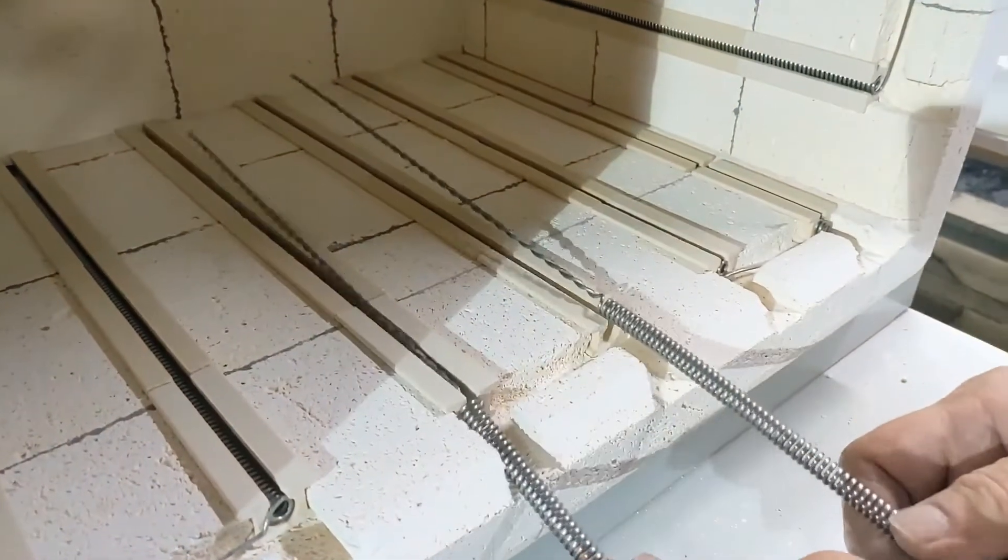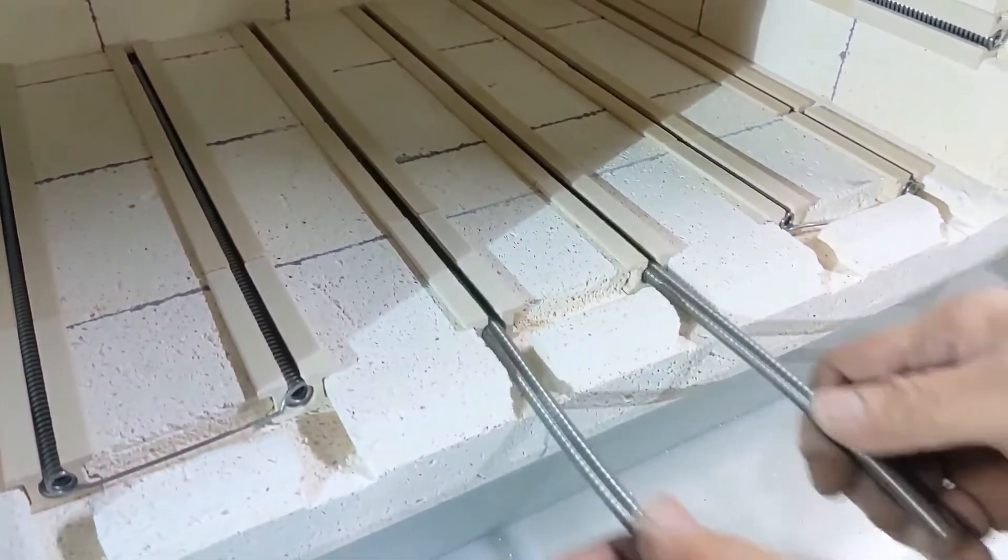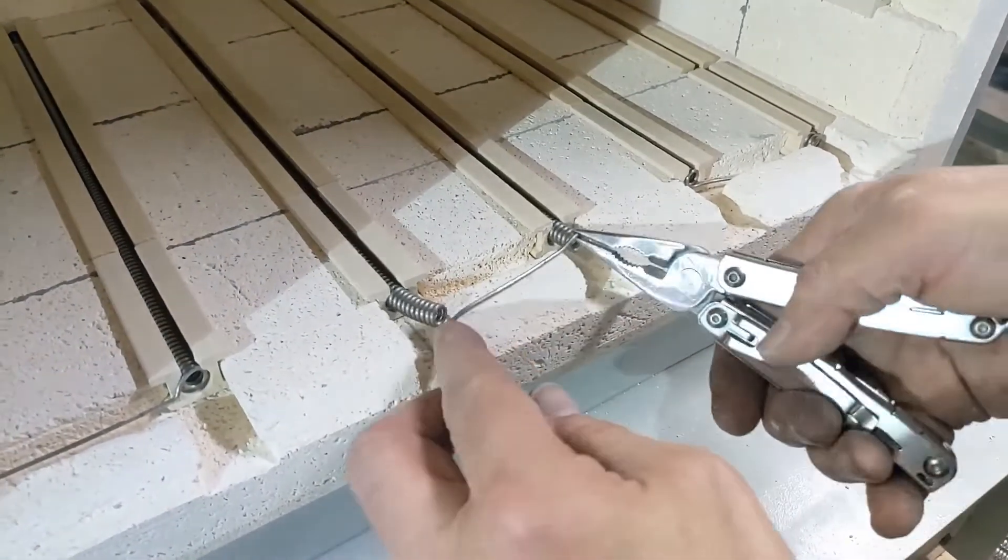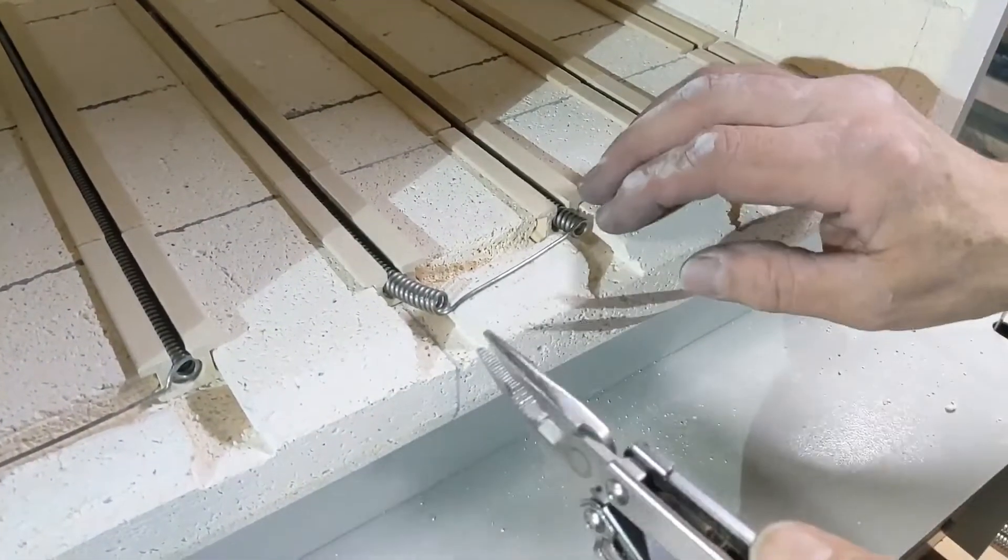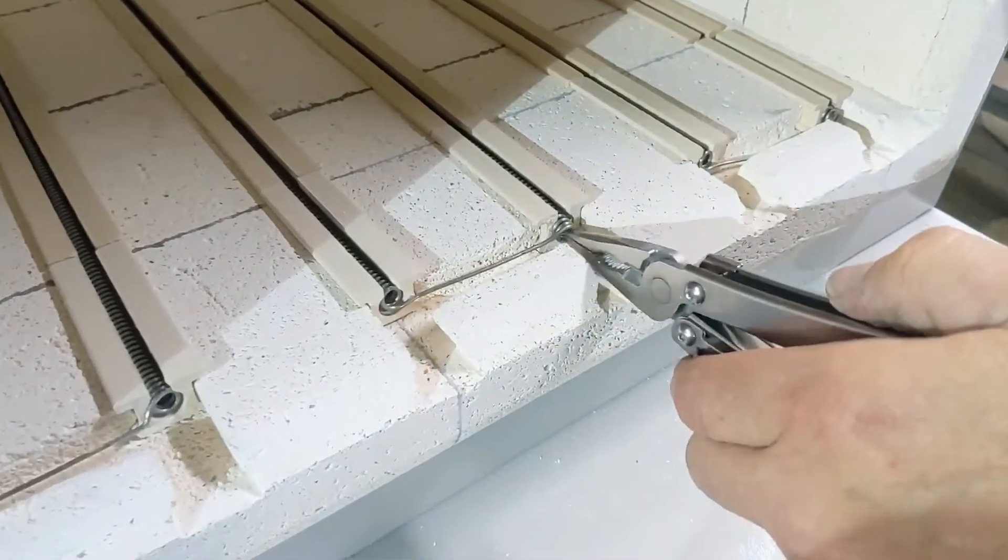With the element modified to fit, insert the heating element into the element holders until the element is just about to hit the front brick of the furnace. Again, using needle nose pliers, lift the element up over the front brick so that the element center slides into the groove.